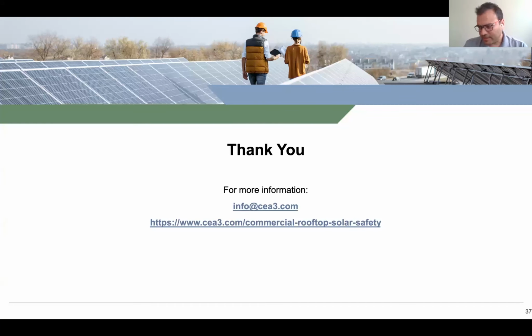That's a really good question. Usually what I'd recommend is, a thermal camera points out an issue, and sometimes you get the definite cause, but if it's a warranty issue you can combine thermal cameras with IV curve tracing. For example, on a 4 megawatt rooftop site, do 100% of the IR testing through thermal cameras, then depending on the results, select a few strings or modules, depending on the scope of work, and do IV curve tracing. Depending on those results, you can then do electroluminescence testing.